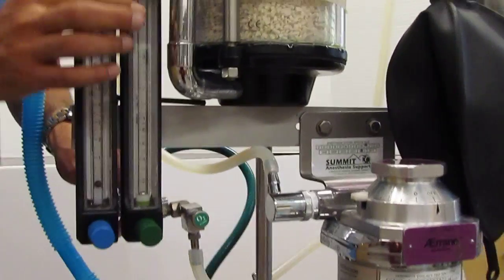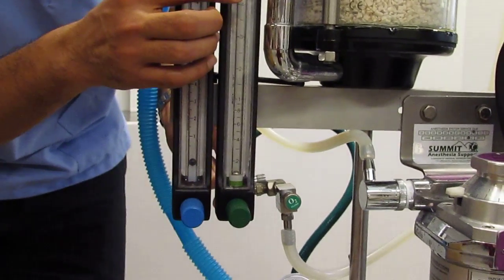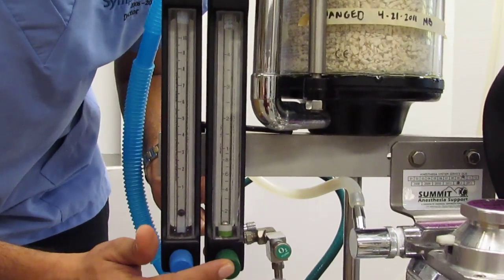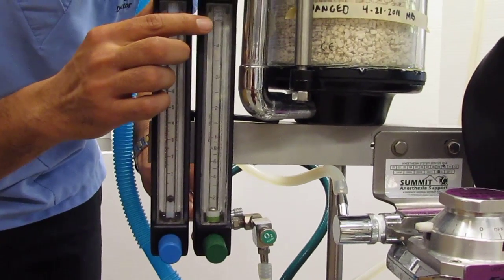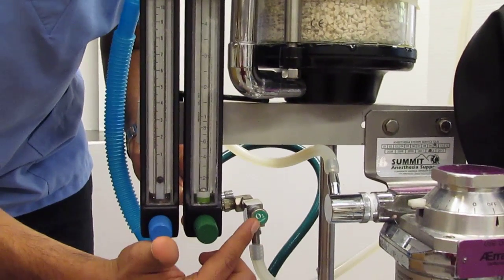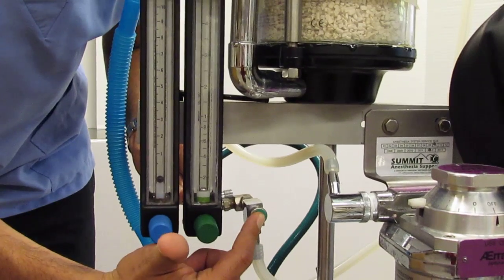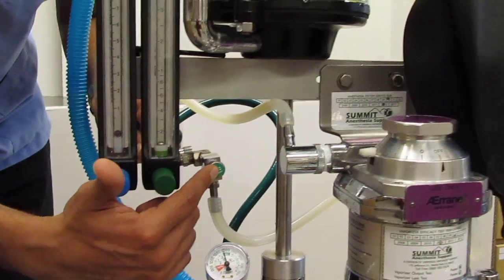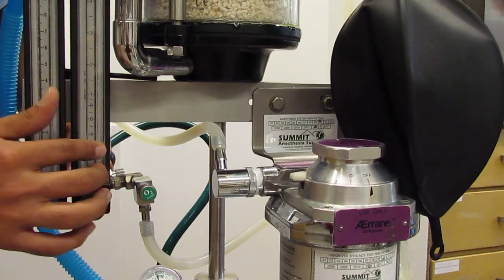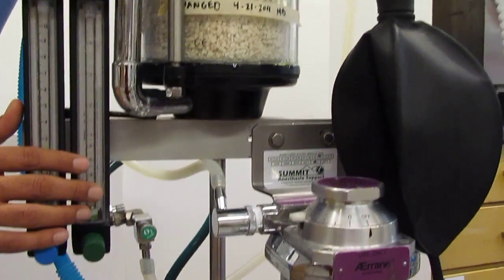So that's one thing that can happen. I can set my oxygen to my vaporizer. The other thing that can happen here is that I can bypass my vaporizer completely via the O2 flush button, okay? That's this button here, okay?